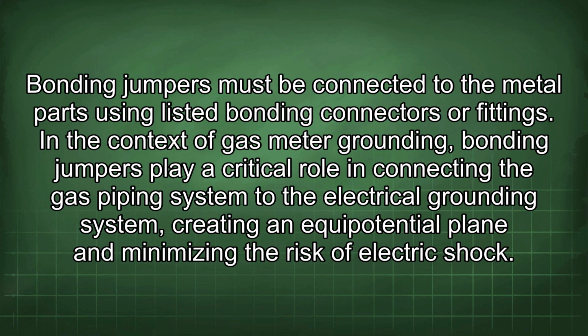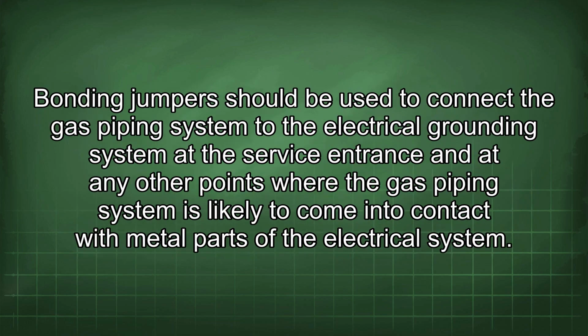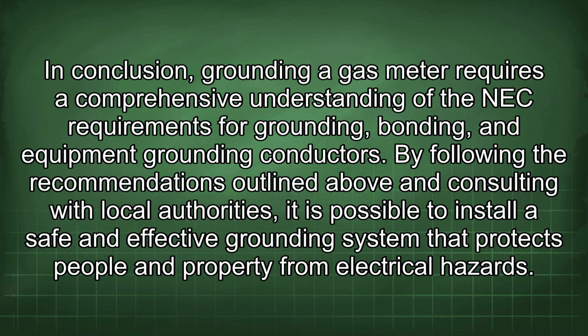In the context of gas meter grounding, bonding jumpers play a critical role in connecting the gas piping system to the electrical grounding system, creating an equipotential plane and minimizing the risk of electric shock. Bonding jumpers should be used to connect the gas piping system to the electrical grounding system at the service entrance and at any other points where the gas piping system is likely to come into contact with metal parts of the electrical system. In conclusion, grounding a gas meter requires a comprehensive understanding of the NEC requirements for grounding, bonding, and equipment grounding conductors. By following the recommendations outlined above and consulting with local authorities, it is possible to install a safe and effective grounding system that protects people and property from electrical hazards.